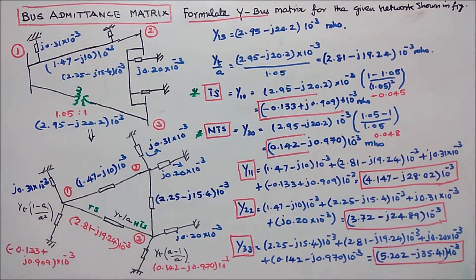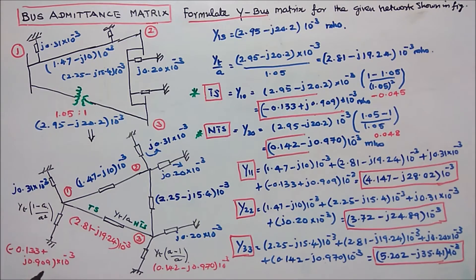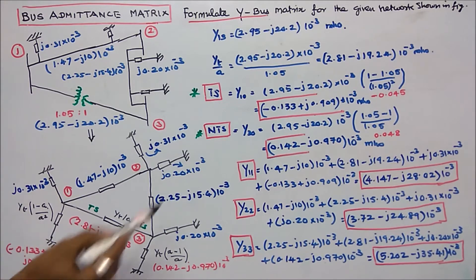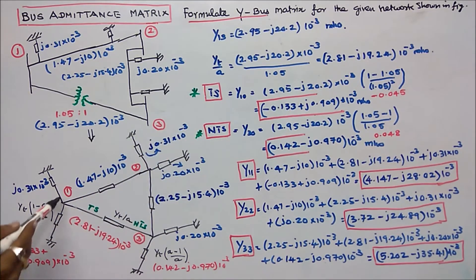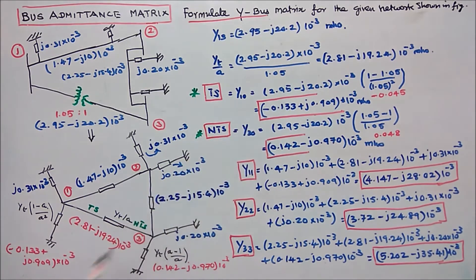The next step is to find the line charging admittance on the tap setting side. The formula is yt into (1 minus a) divided by a squared, where a equals 1.05 and yt equals 2.95 minus j20.2 into 10 power minus 3. The tap setting side line charging admittance is minus 0.133 plus j0.909 into 10 power minus 3.